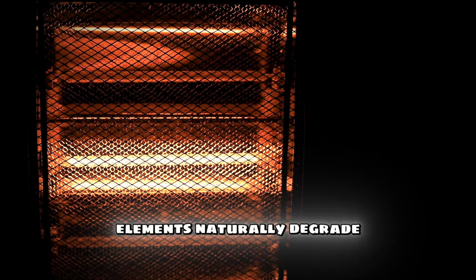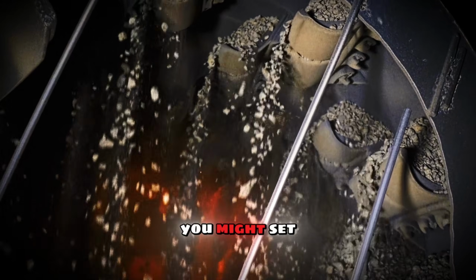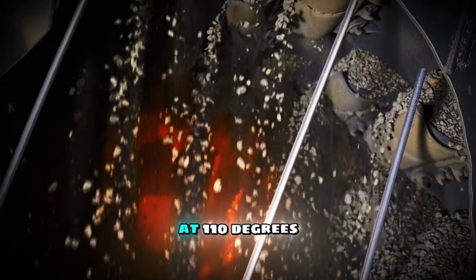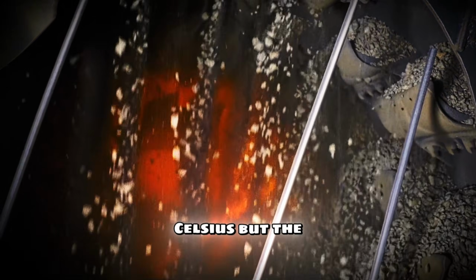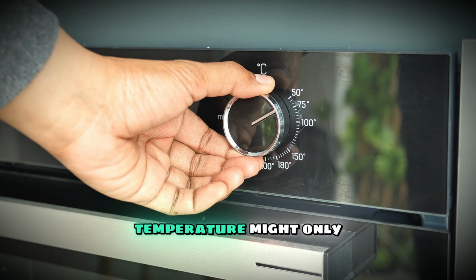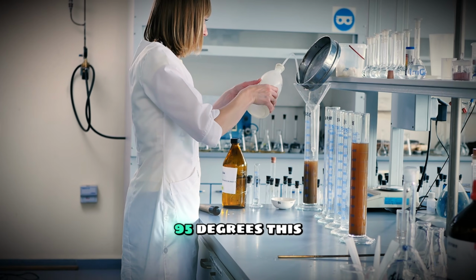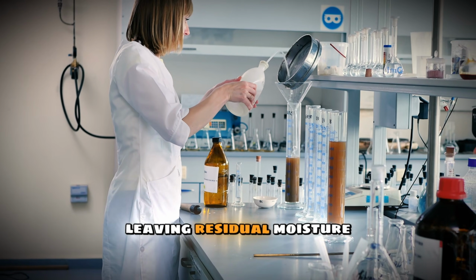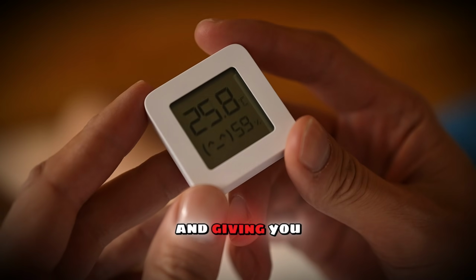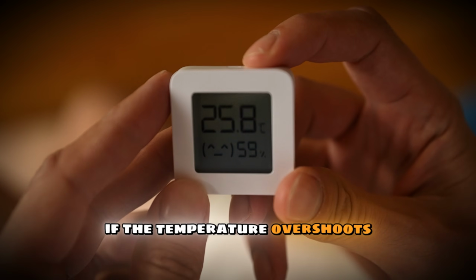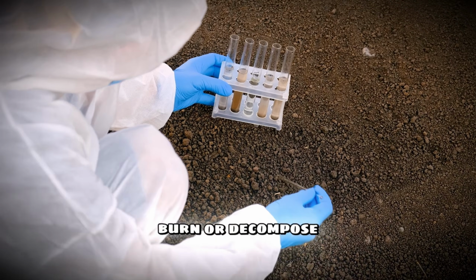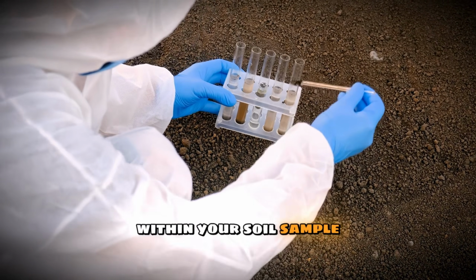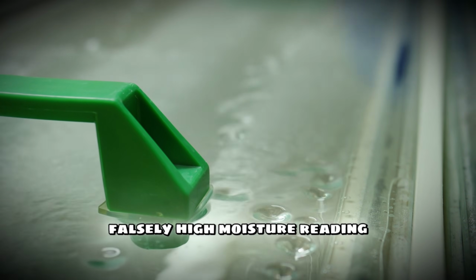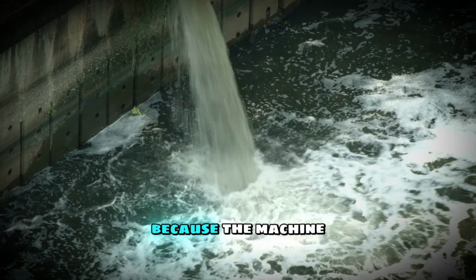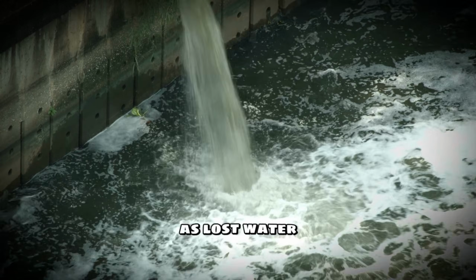Over time, heating elements naturally degrade. You might set the machine to dry your aggregate sample at 110 degrees Celsius, but the actual chamber temperature might only be reaching 95 degrees. This results in underdrying, leaving residual moisture in the sample and giving you a falsely low moisture content percentage. Conversely, if the temperature overshoots, you might actually burn or decompose organic materials within your soil sample, leading to a falsely high moisture reading because the machine interprets the loss of burned mass as lost water.